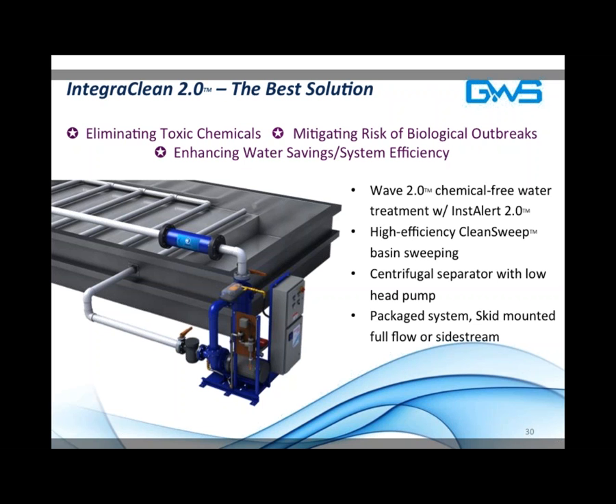We have a table that calculates required flows through the reaction chamber itself, and most often those flows, obviously they depend on pipe size, but we are typically looking to stay within 12 or 13 feet per second. And in most cooling tower applications, we're well within that range. Evaporative condensers, of course, run a little faster. They run a little higher. And so if flows exceed that slightly, we're not terribly worried because the turnover rate in those systems is very high. So I would say that the treatment rate within the Wave itself is well within the parameters of most operating conditions of the flow ranges of cooling towers.